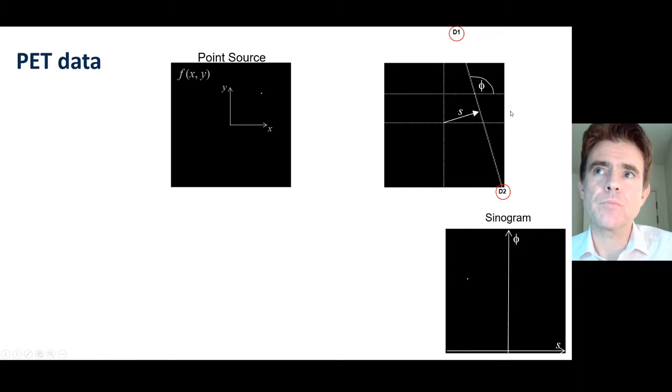We can characterize that line by S and phi. With the rotated system, the Y-axis was in that direction, so S is actually a negative value here. Here's the S-axis on the sinogram. We're plotting one count at that particular S and phi location. This is a 2D function. S and phi corresponds to a line through the scanner field of view.